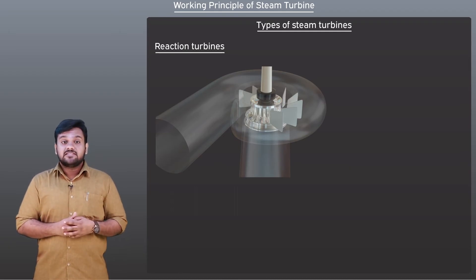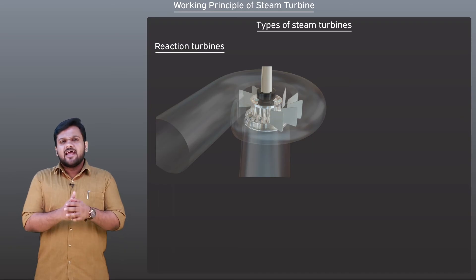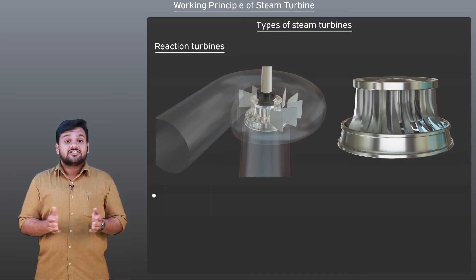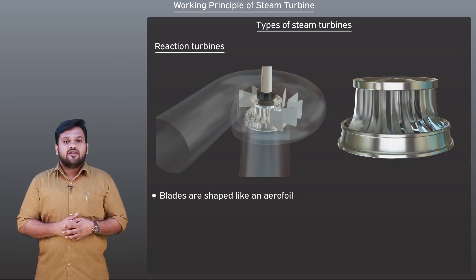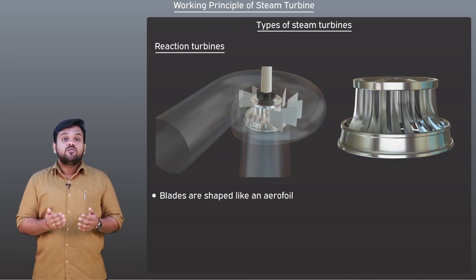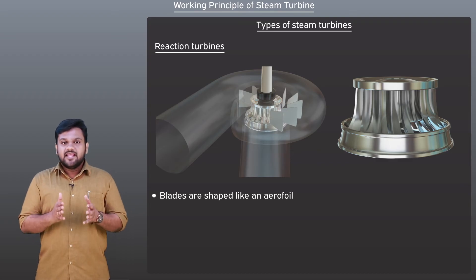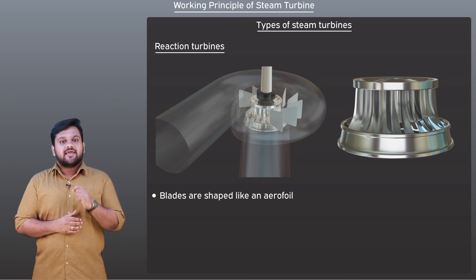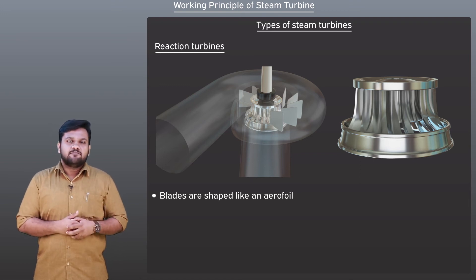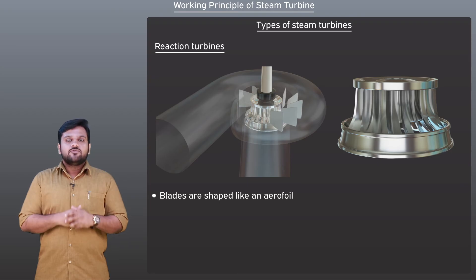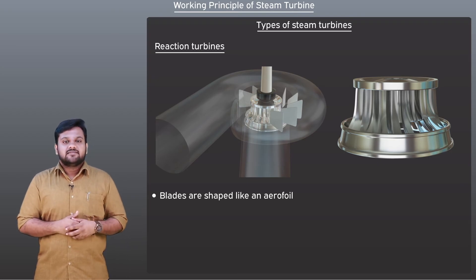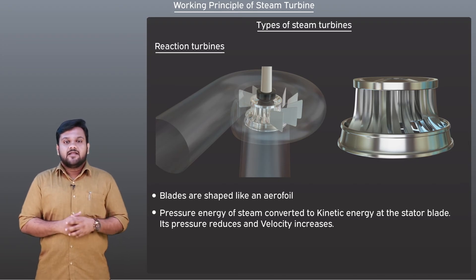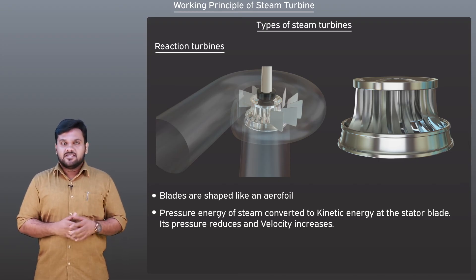A reaction turbine works a bit differently than an impulse turbine. The blades of a reaction turbine are shaped like an aerofoil with a slight bucket curve towards the end. Steam enters through a pipe, usually in a radial direction. A set of fixed blades guide the steam through a set of moving blades. The pressure energy of the steam is converted to kinetic energy at the stator blade, reducing its pressure and increasing its velocity.